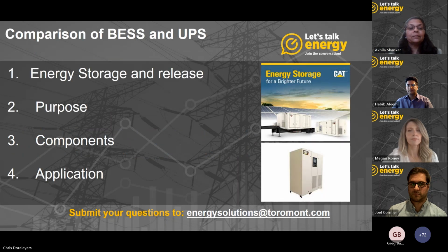So in terms of energy storage and release, a UPS is designed to store small amounts of energy and release it over a short period of time. A UPS provides immediate short-term power during a power outage or during power fluctuations. This typically lasts anywhere from a few minutes to a few hours, whereas the battery energy storage system is designed for energy management. It provides high stored energy, that is high power over longer periods of time, ranging from hours to days.